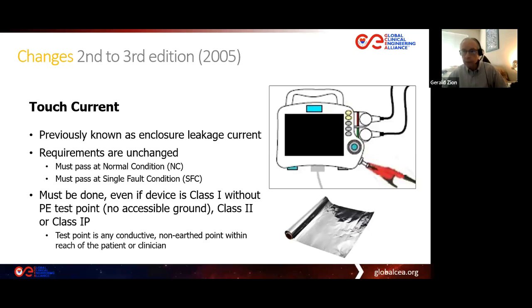So class, there is a new situation that we face out here now with medical devices that are completely enclosed in plastic. There is no conductive test point available. And by the way, there is no protective earth test point either. And there will not be any in any case under a Class 2, which is double insulated. You will only have 2 prongs on the power cord, or a Class IP, meaning internal power, like a battery powered medical device.